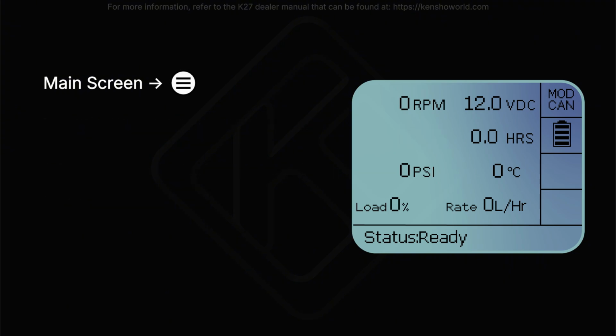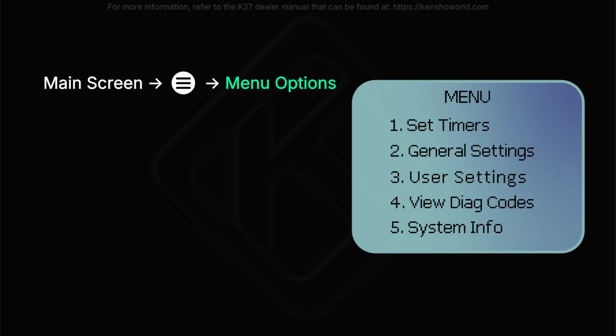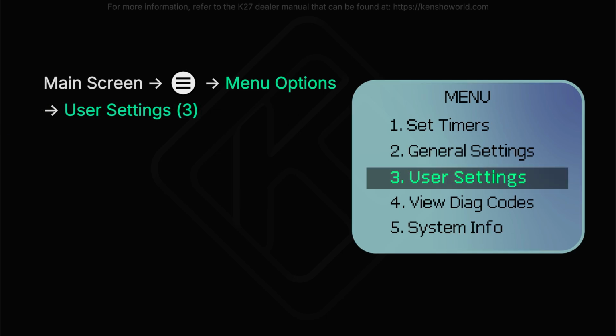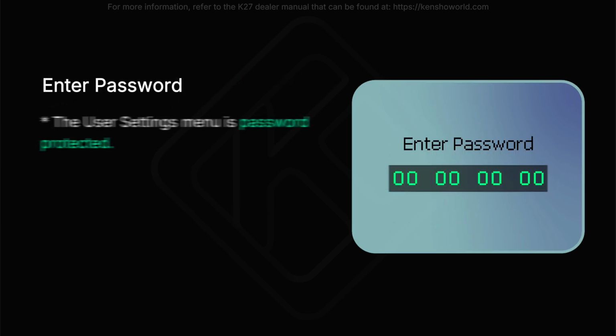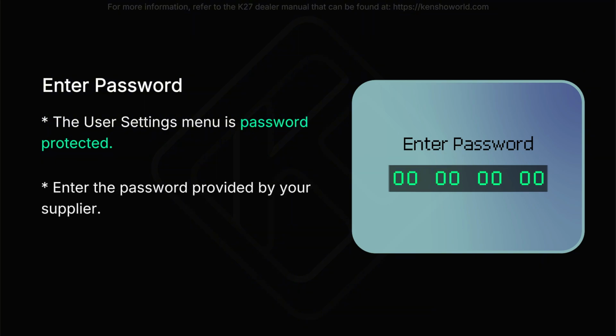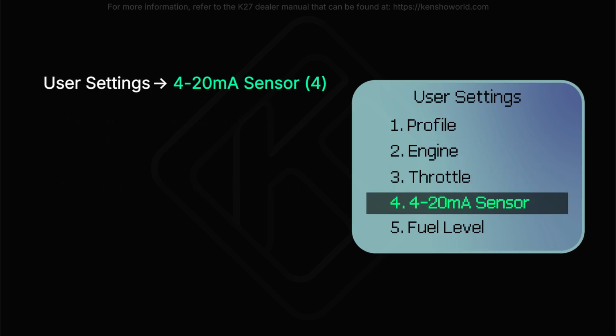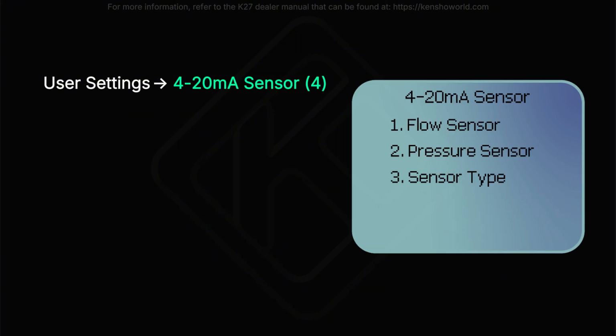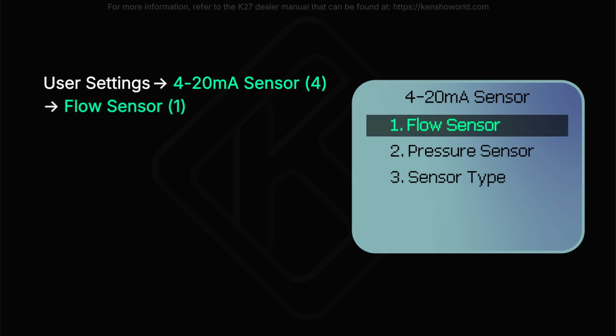Press the menu button to display the menu options. Then, select User Settings. The User Settings menu is password protected. Enter the password that was provided by your supplier. In the User Settings menu, select 4 to 20 mA sensor. From this screen, you are able to select the primary 4 to 20 mA input. For this example, select Flow Sensor.